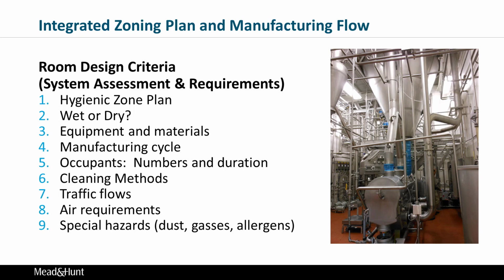What's the manufacturing cycle look like? Is it all 70 degrees all the time, or do I have to shut everything down, and when I'm cleaning, it's a steam room basically for about 6 hours, and then I have to get back in production? What happens in the middle of summer when it's 104 degrees outside, and I have to keep 40 degrees in this area, and my engine room is strained? What are all those peak conditions, and how do I get through those peak demand times? Who's in there for how long? What methods are they going to use to clean? What are the traffic flows? Who's dragging what through there?